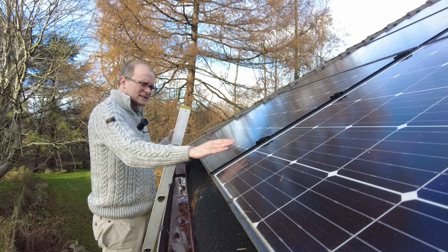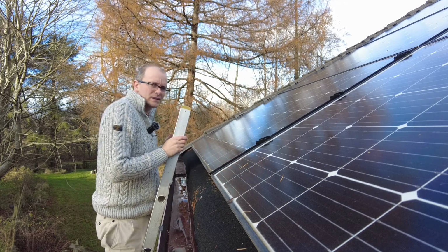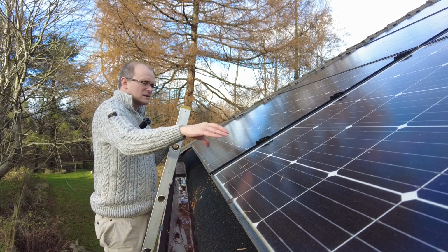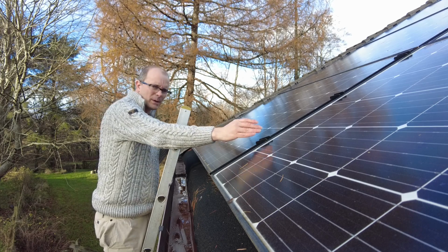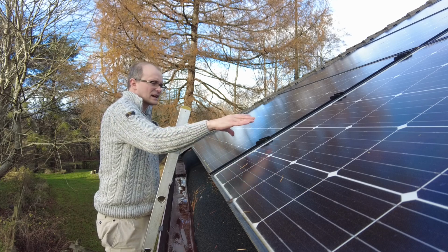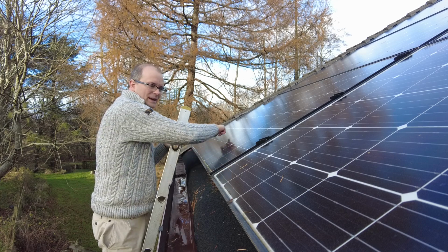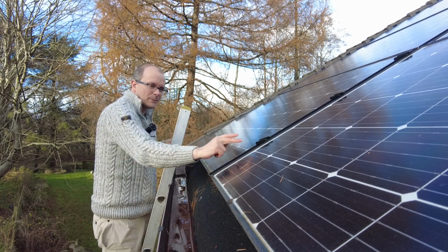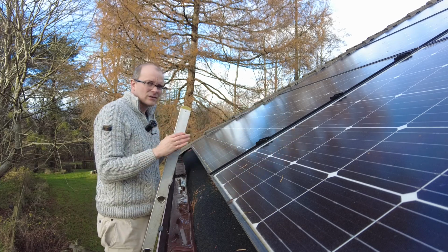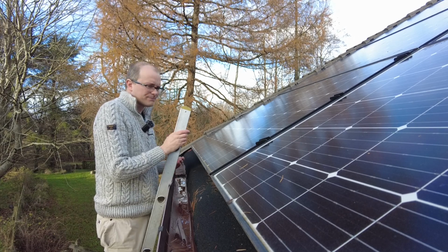Now, these cells are all connected in series all the way up the solar panel module. So if one fails, you've got bypass diodes, and each section of cells can be bypassed. So you can have a string which goes from here and back to here again, and you can have a bypass diode from there to there, and likewise from there to there. So you've got 3 separate circuits which could be bypassed.